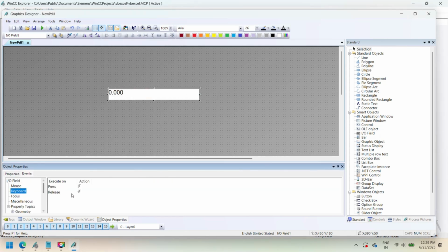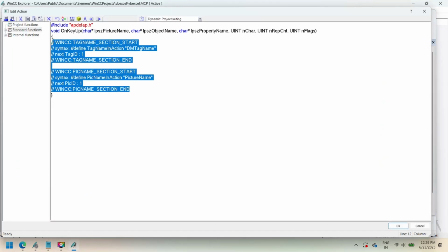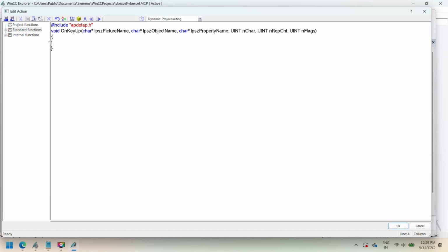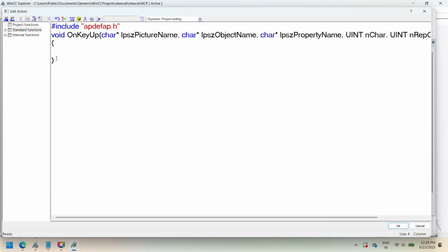In Siemens WinCC SCADA, you can design a simple and effective alarm monitoring screen using graphical components to visualize alarm status clearly for the operator. The input-output field can be used to manually test the alarm ranges during runtime or connect to a PLC tag in real deployment. Use an action script in WinCC SCADA to control alarm indication based on the temperature value.